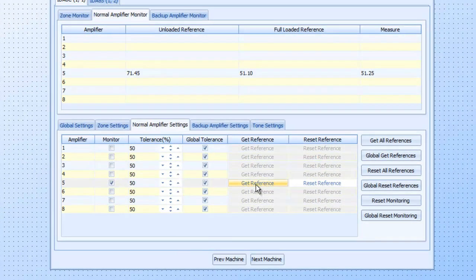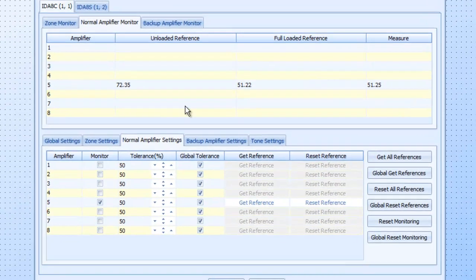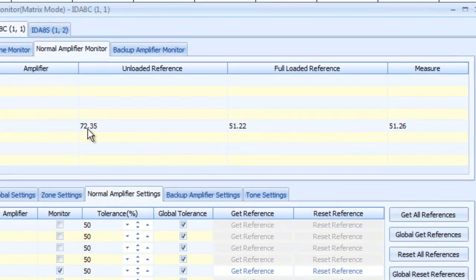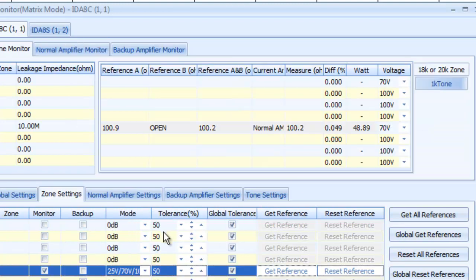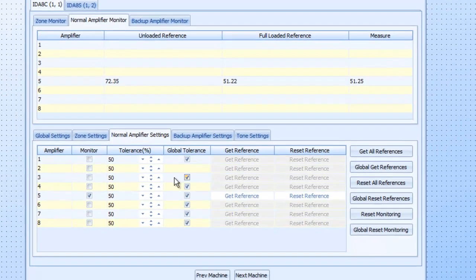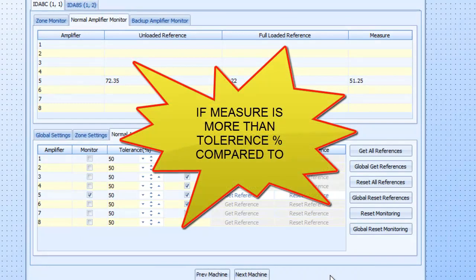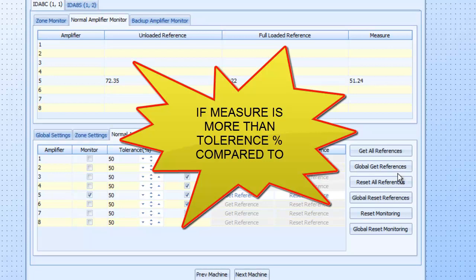If we go to our normal amplifier, let's get a reference on our amplifier. There we go. And the amplifier reads an unloaded reference. And it reads it under full load reference. And that's the measurement that it's reading currently. So as long as this measurement stays within your tolerances that you set here in percentages, you are nice. The minute it goes outside of that tolerance that you set for each circuit is when you're going to get a fault.